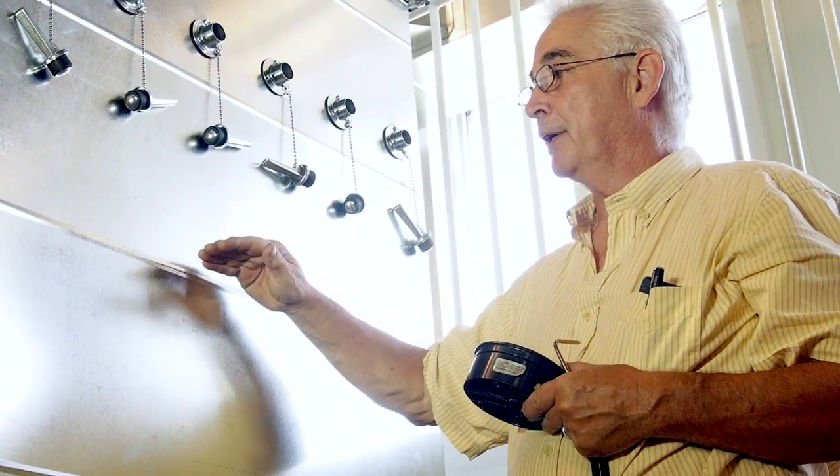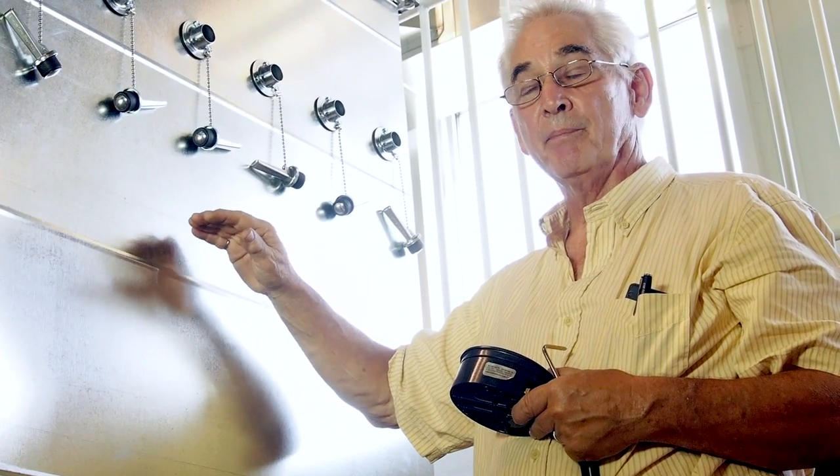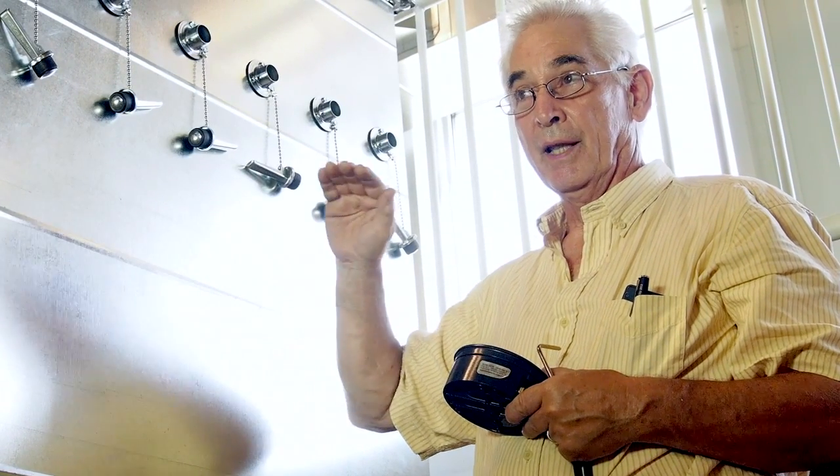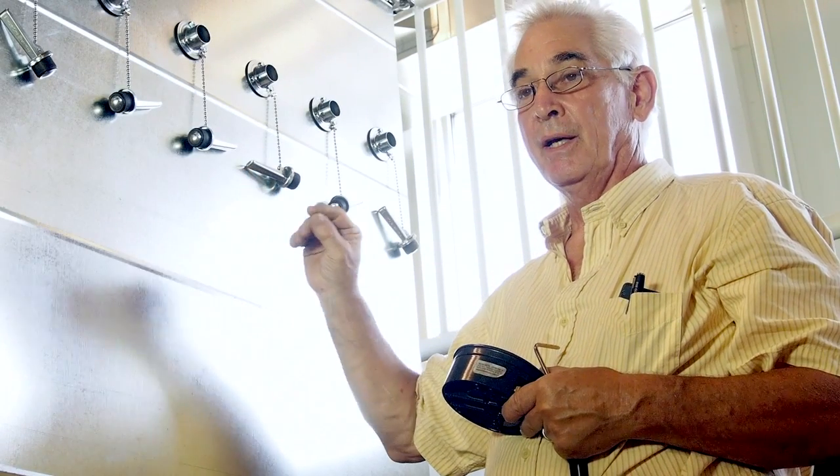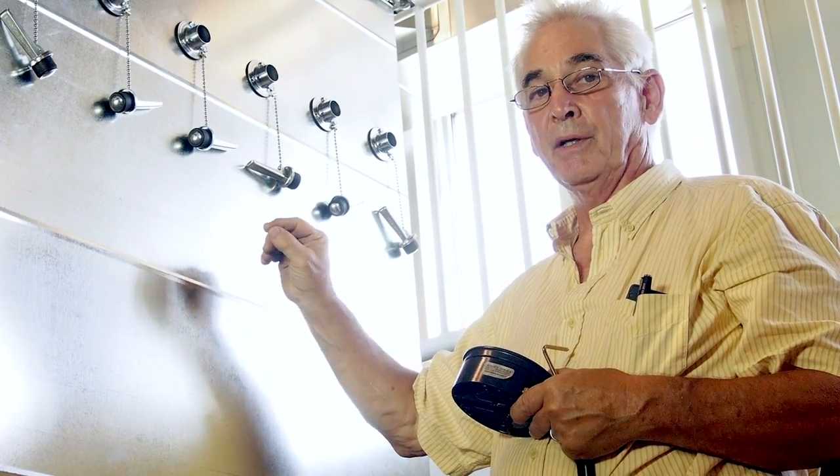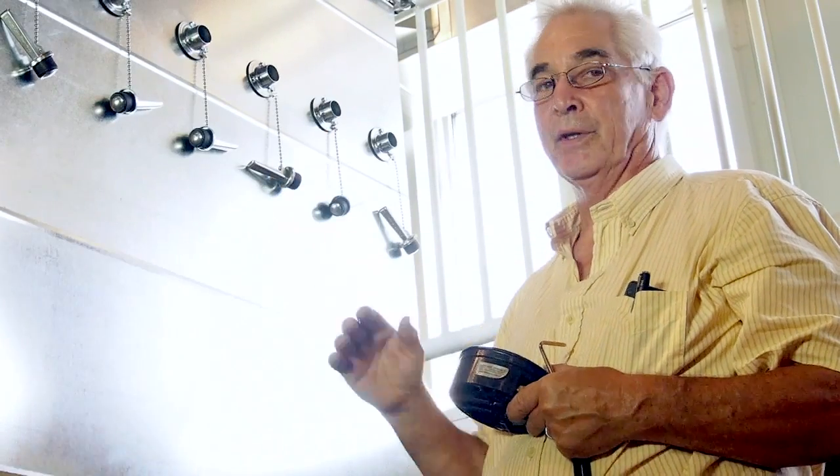So, if we calculated 1,100 feet per minute, 1,100 feet per minute times 4 feet squared is 4,400 cubic feet per minute flowing through this duct.